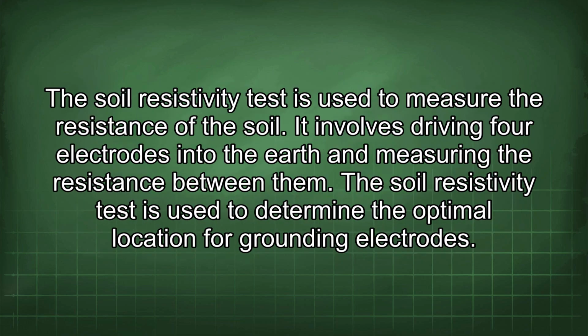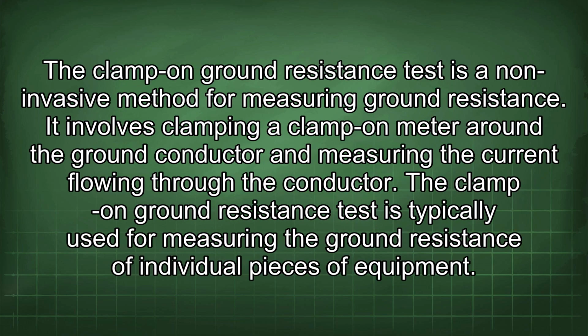The soil resistivity test is used to measure the resistance of the soil. It involves driving 4 electrodes into the earth and measuring the resistance between them. The soil resistivity test is used to determine the optimal location for grounding electrodes. The clamp-on ground resistance test is a non-invasive method for measuring ground resistance. It involves clamping a clamp-on meter around the ground conductor and measuring the current flowing through the conductor. The clamp-on ground resistance test is typically used for measuring the ground resistance of individual pieces of equipment.